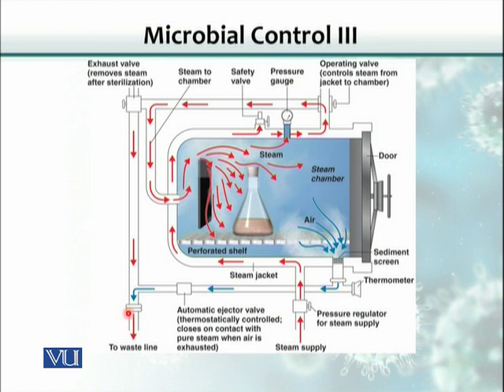This is a schematic diagram of an autoclave where steam is produced in ducts and then injected under pressure. The steam is enclosed in a small container, creating pressure. At 15 psi, the temperature achieved is 121 degrees Celsius. Keeping the object at 15 psi and 121 degrees Celsius for 15 to 20 minutes is enough to achieve complete sterilization.